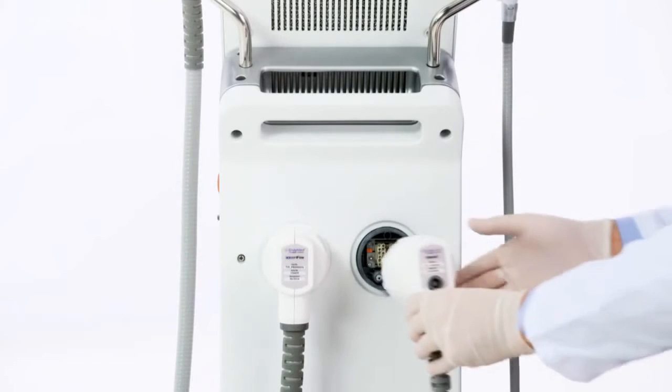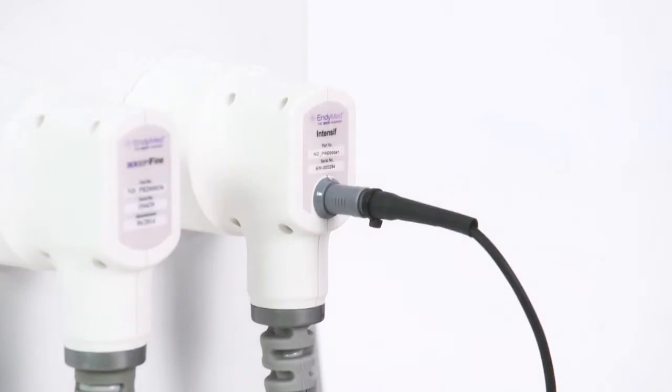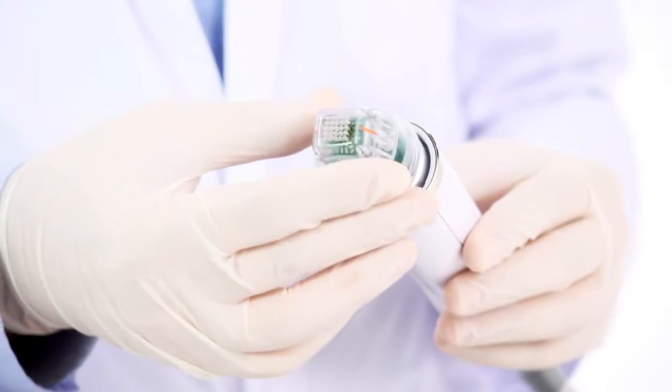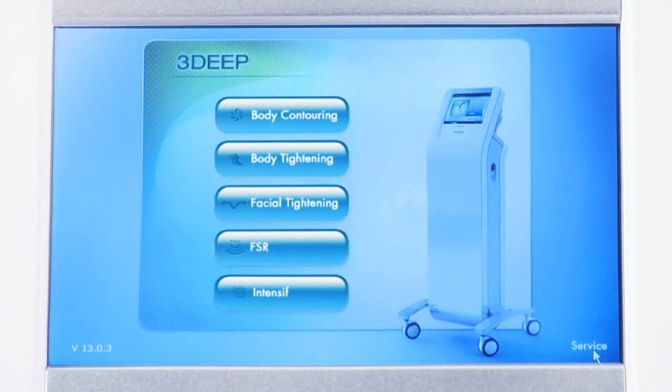Connect the Intensif handpiece to the right connector when looking from the rear side of the system. Then connect the foot switch to the handpiece connector. The Intensif treatment tip is intended for single use only. Connect the tip by using a circular motion until it is in place. When the menu screen opens, select the Intensif application.